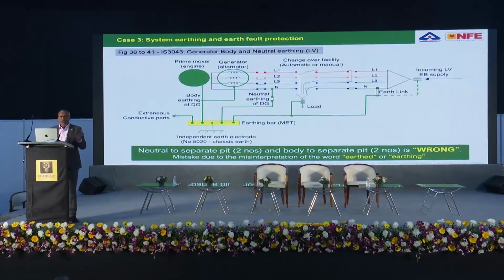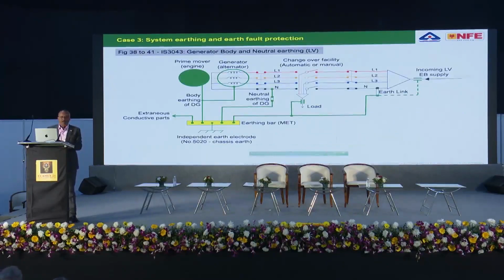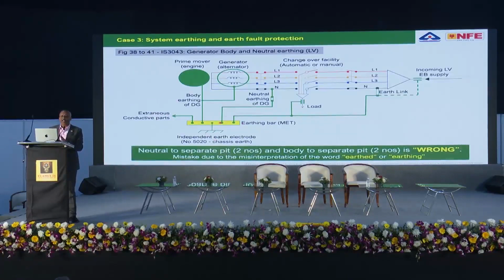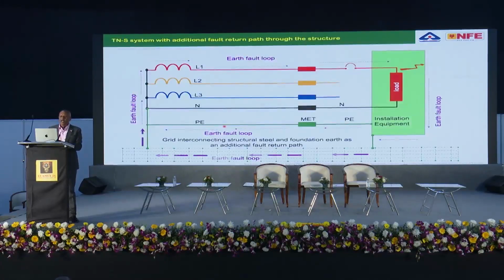This picture I just took from IS 3043. It explains how to make an earthing of a DG and mains changeover. You have a common bus bar. You connect all dead metal parts to the common bus bar. Neutral also you connect to the same bus bar through a link. That is what is required. So this information has existed in the standard for a longer time.